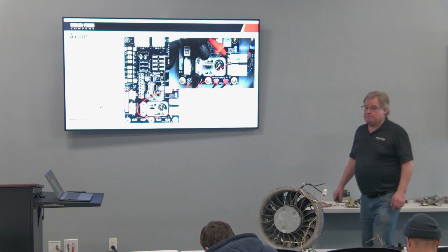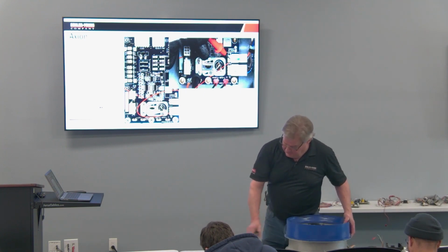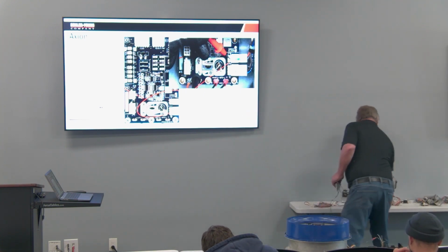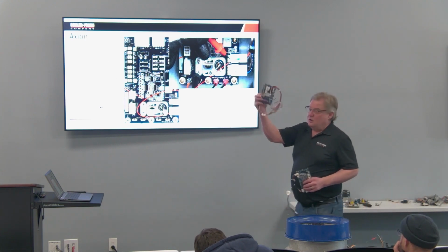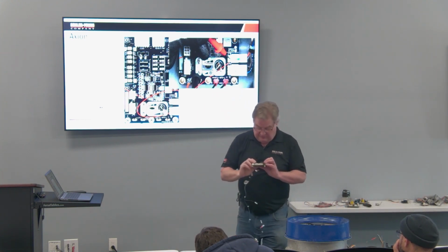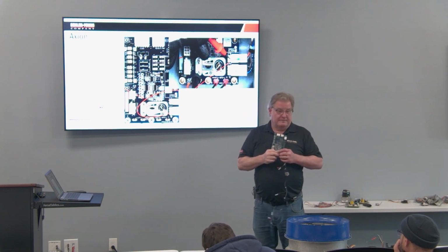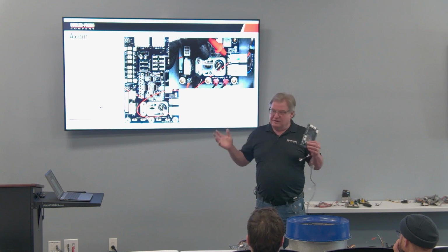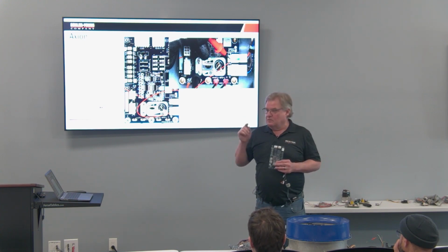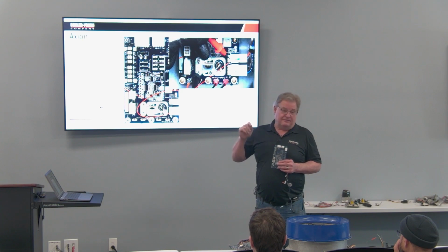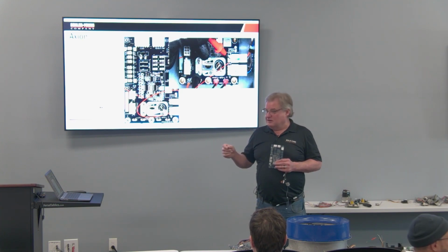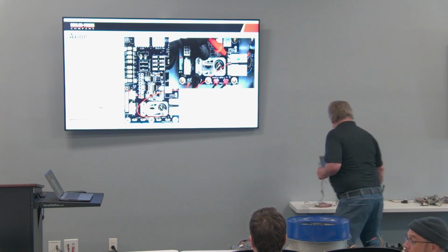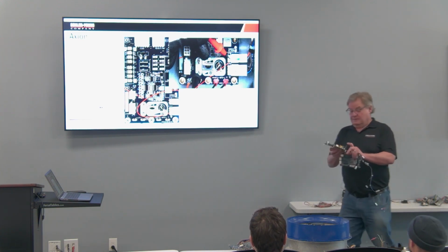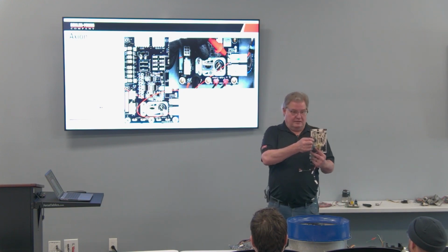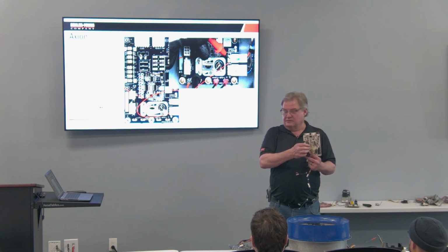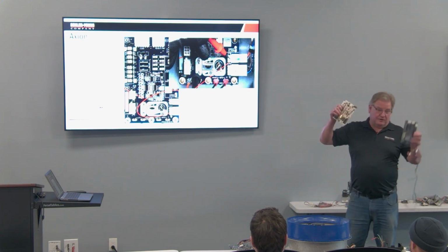You ever had the board side fail? Yes. Okay. Unlike the old 580, this is the old belt drive board. There's no logic on this board at all. There is a relay circuit down here. So every furnace, every rooftop unit you guys have ever worked on, there's a relay on the furnace control board that, when you energize R to G, turns the blower on, right? When we get to the gas control board, look, there's two relays: low speed, high speed, G, Y2. Either way, there's still a relay on the gas board, but there's a relay on here too.